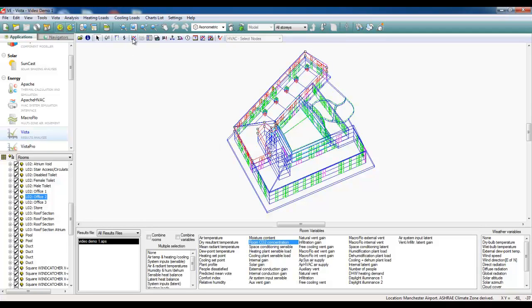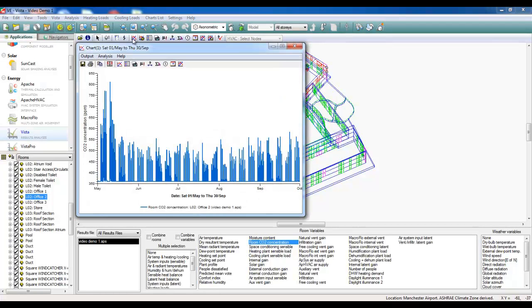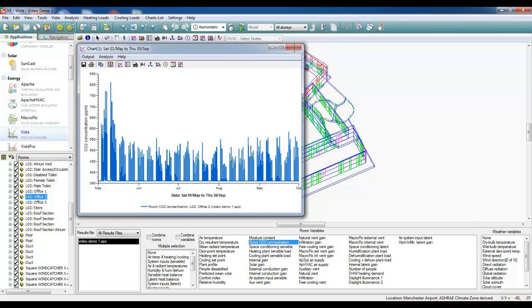I can also check my air quality. If we're looking at the CO2 concentrations, here it doesn't exceed 850 ppm over the course of the non-heating season, which again is what we would expect.